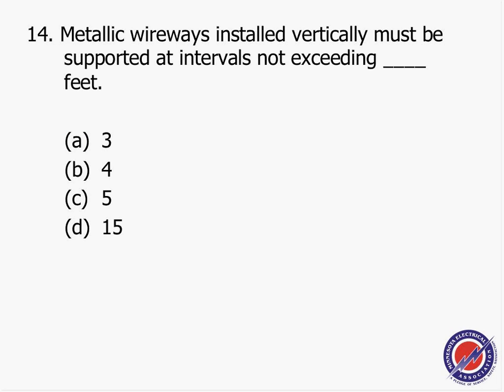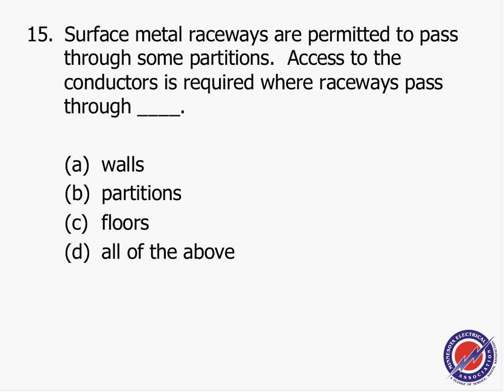Number 14, my friends, metallic wireways installed vertically must be supported at intervals not exceeding 4 feet, and we have D. Number 14, we have D is 15 feet, right from the NEC code book, no mimic.